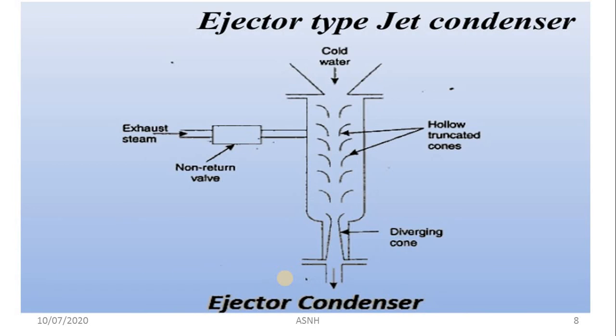So there is no need of a condensate extraction pump in the case of the ejector type condenser, and that is its main specialty. When the steam and the water come in contact with each other, a phase change takes place directly due to the latent heat of condensation, and we get condensate at the end, and that condensate finally passes through the divergent cone. Because of that, the kinetic energy of the mixture gets converted into pressure energy, and the condensate is collected in the hot well through the divergent cone in the absence of the condensate extraction pump.